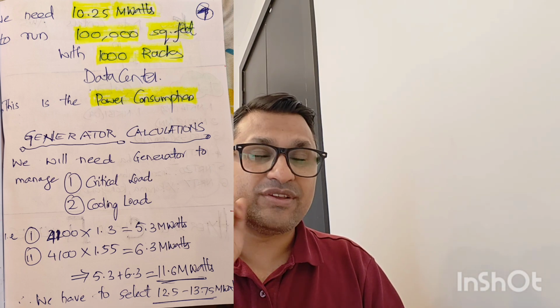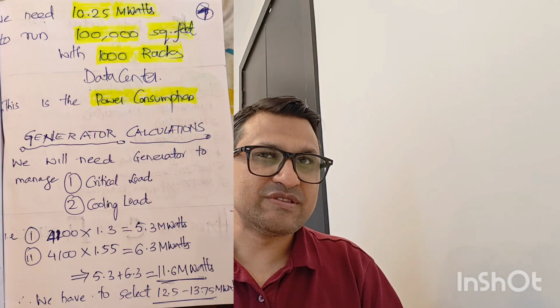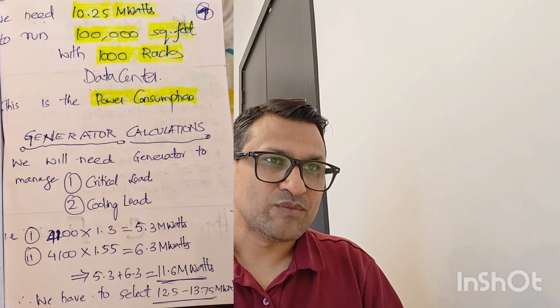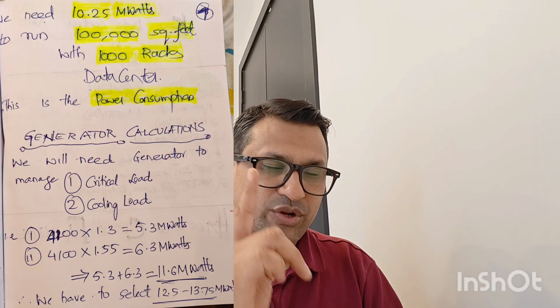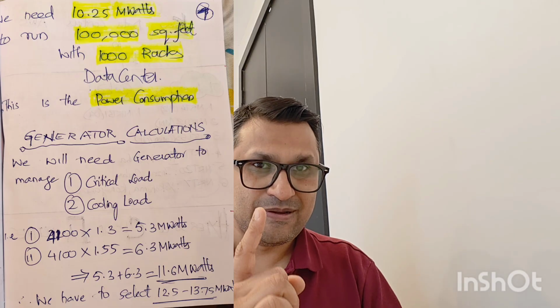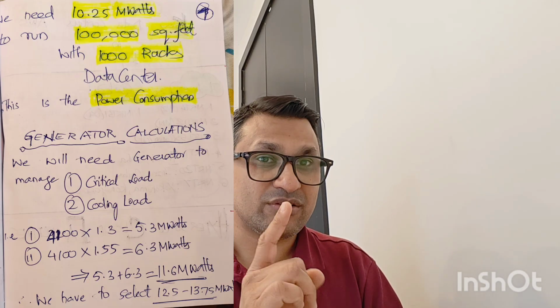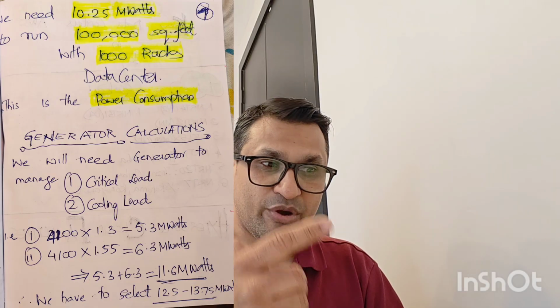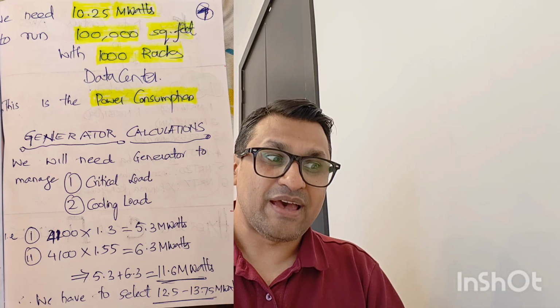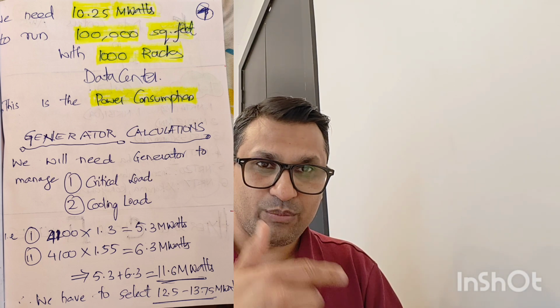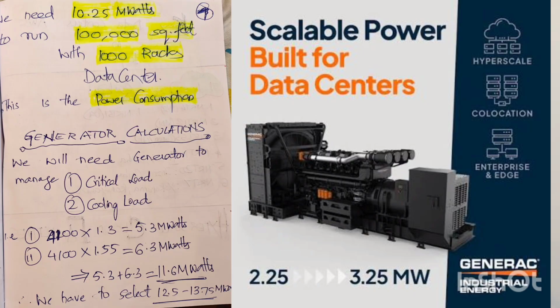Now remember this: when we are designing a generator for the critical load, which is only the equipment, servers, racks, and other equipment, we multiply by 1.3. So 4100 times 1.3 gives us 5.3 megawatts. For the cooling load, we multiply by 1.55. I'll explain in future videos why we use these multiplication factors: 1.3 for critical load and 1.55 for cooling load. 4100 times 1.55 is 6.3 megawatts. So you add 5.3 plus 6.3, you have 11.6 megawatts. So we have to select a generator with a rating to handle 12.5 to 13.75 megawatts. That is the size of the generator required.